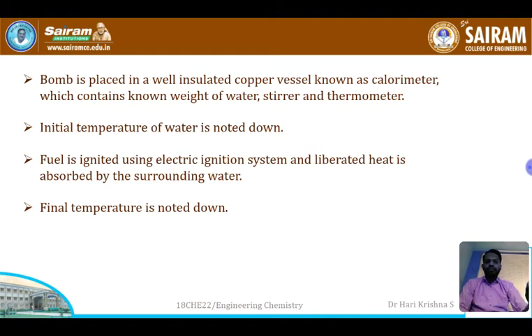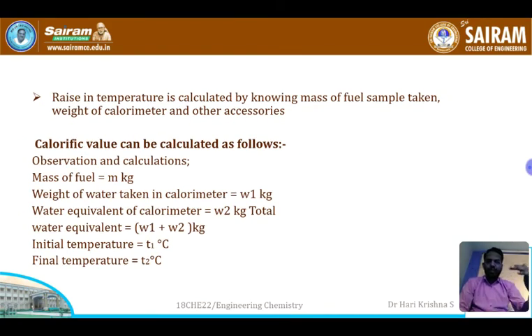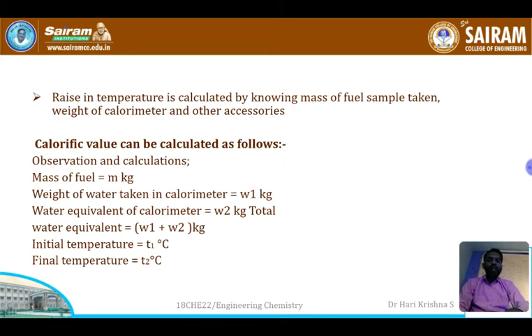To ensure the heat is distributed uniformly throughout the water, a stirrer is used. Once the temperature stabilizes, the final temperature is noted down. By knowing the rise in temperature, the temperature difference, the mass of the fuel, and the weight of the calorimeter and other accessories, we can determine the calorific value of the known mass of fuel.